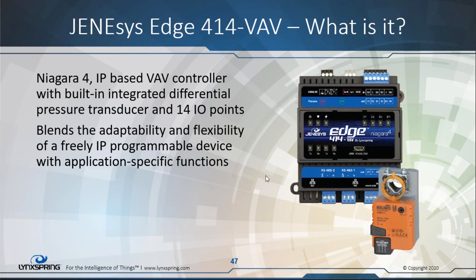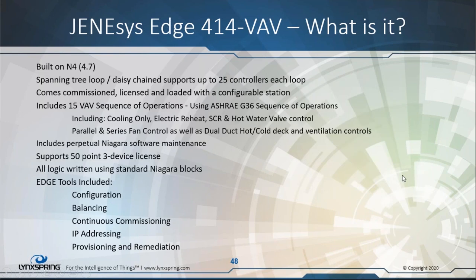Next, please. So a little bit to understand about the VAV controller itself: it can be daisy chained using spanning tree protocol. Each daisy chain is limited to up to 25 controllers per loop, which we call a loop. One end connects to an edge gateway and the other end connects to the edge gateway as well, so we have communication back and forth through that loop over 25 controllers.